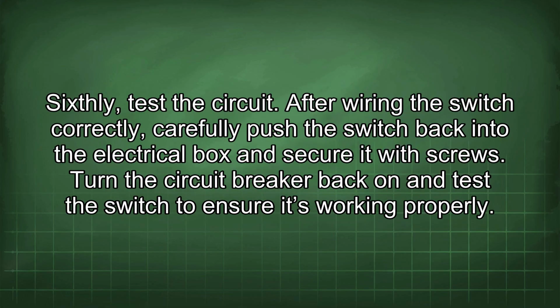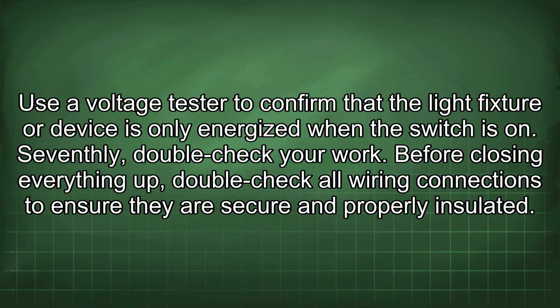After wiring the switch correctly, carefully push the switch back into the electrical box and secure it with screws. Turn the circuit breaker back on and test the switch to ensure it's working properly. Use a voltage tester to confirm that the light fixture or device is only energized when the switch is on.